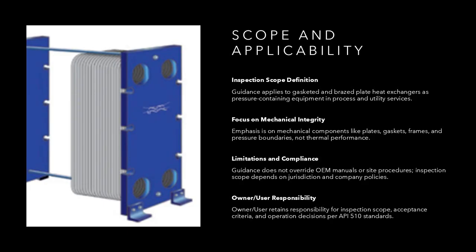The guidance does not replace original equipment manufacturer, OEM, manuals, design specifications, or site-specific procedures, which always take precedence where more restrictive. Inspectors are reminded that certain PHE designs may have limitations on disassembly, non-destructive examination, or repair options. The applicability also depends on jurisdictional and company requirements, and the owner/user retains ultimate responsibility for inspection scope, acceptance criteria, and continued operation decisions in accordance with API 510.